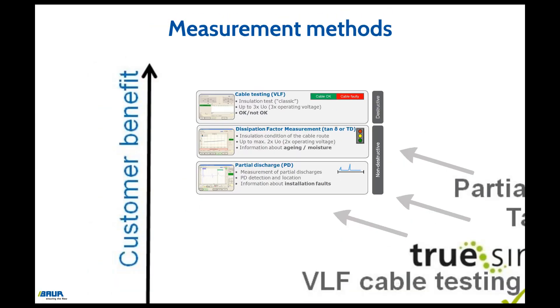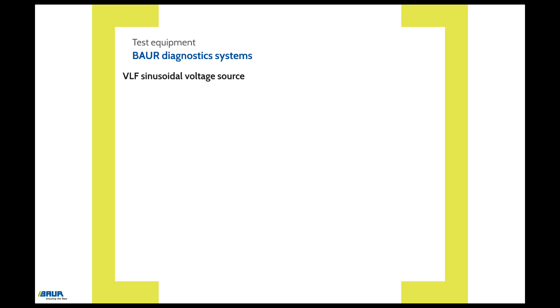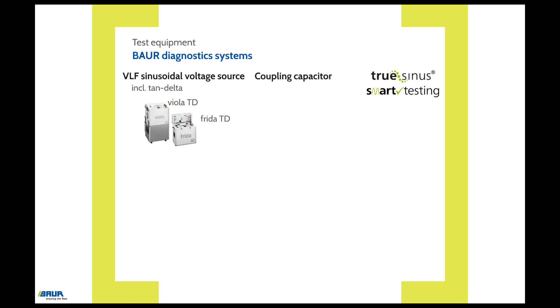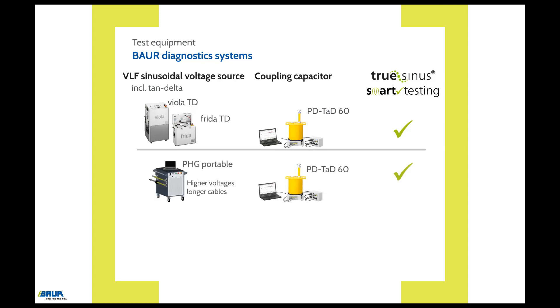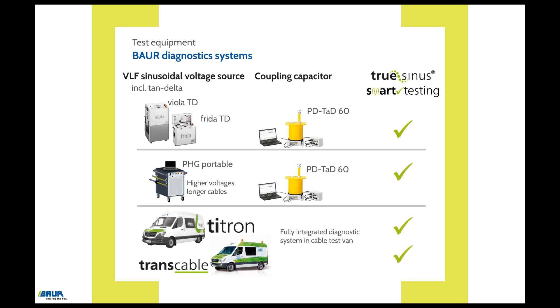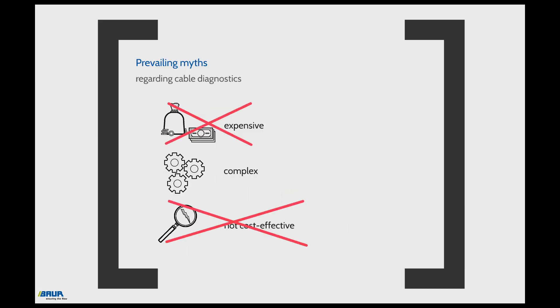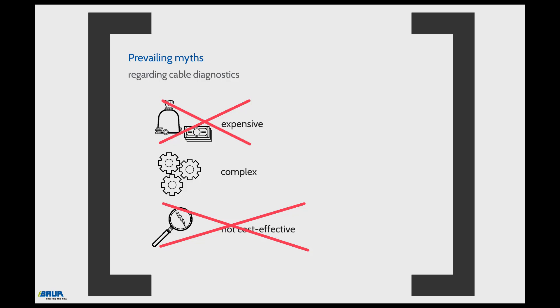Baur diagnostic systems include a VLF sinusoidal voltage source with integrated TAN-delta function, a coupling capacitor for partial discharge testing, and Baur VLF true sinus technology. These systems range from smaller variants such as the Frida TD or Viola TD with PDTAD60 coupling capacitor and a PC for controlling the system, through alternative VLF voltage sources such as the PHG for higher voltages and longer cables, to fully integrated diagnostics in the cable test vans TITRON or TransCable. Today's diagnostic systems are already very compact, handy, flexible, and user-friendly, offering a high level of significance for various application cases.